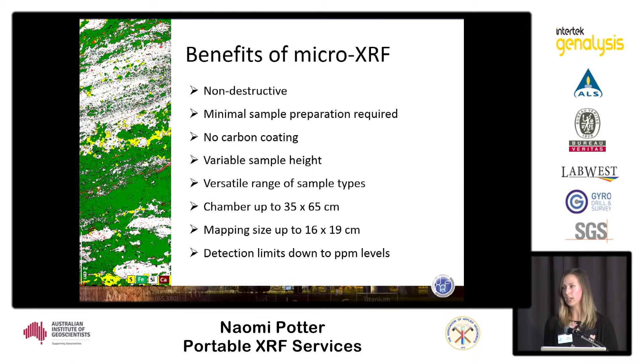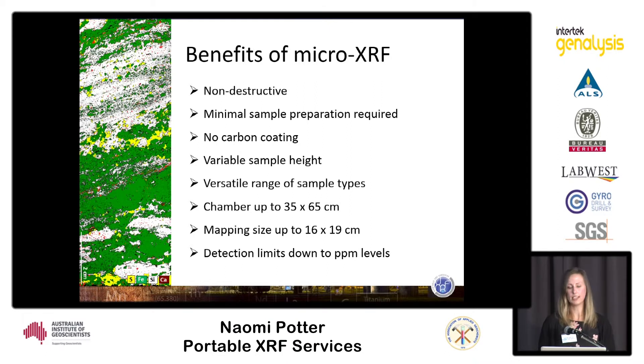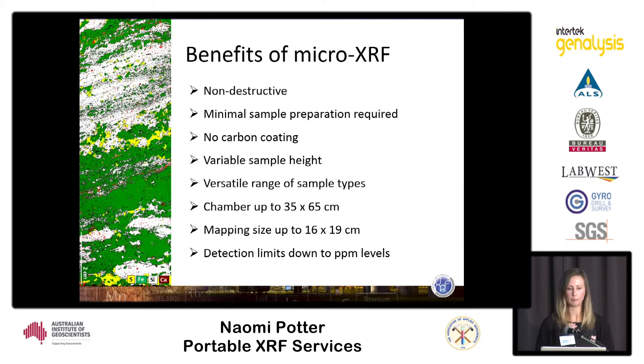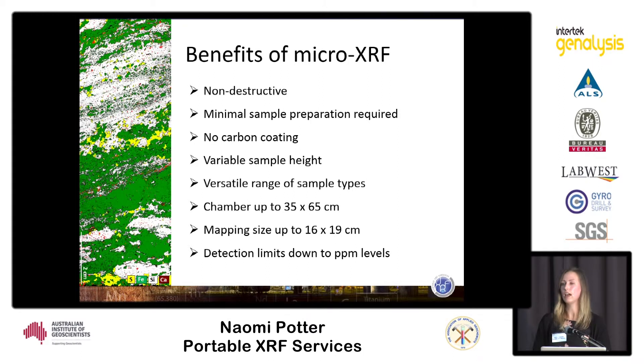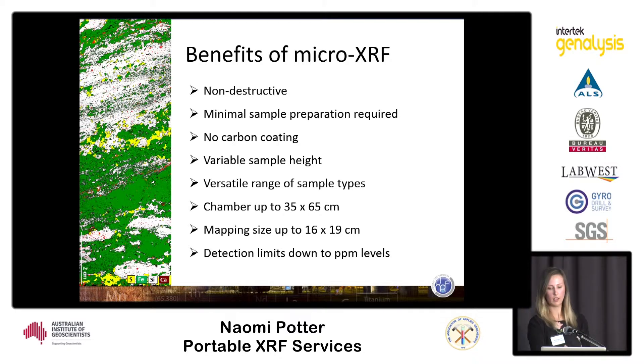If you have a sample bigger than the mappable area, you can still analyze it — it just needs to be moved after the first part has been scanned. You can also scan multiple pieces of core or samples within the same time frame. The detection limit goes down to ppm level for transition and heavier elements, but lighter elements such as sodium and magnesium are still in the weight percent range.